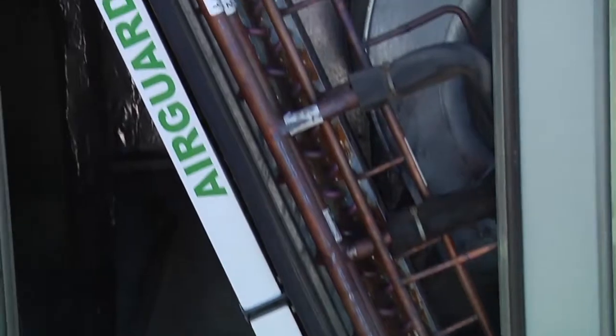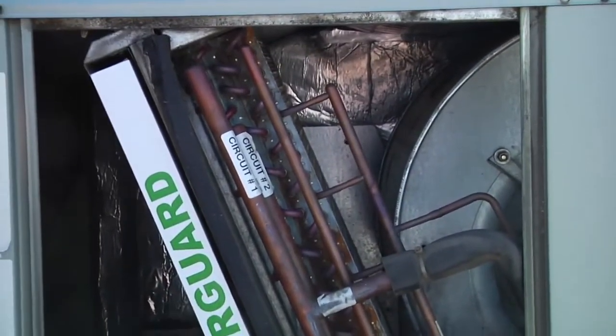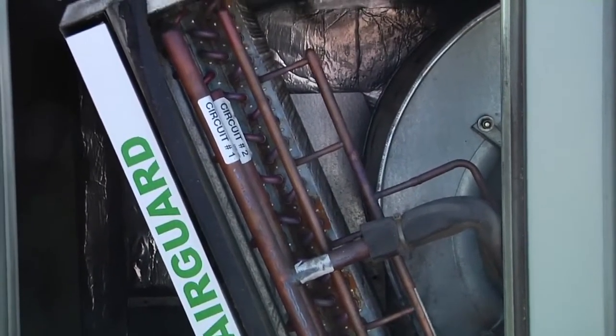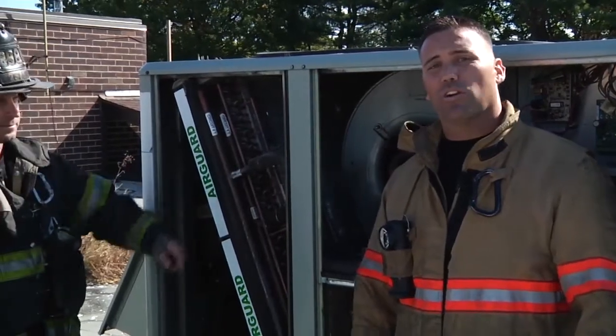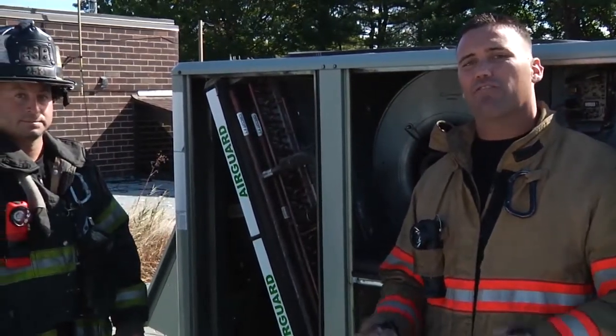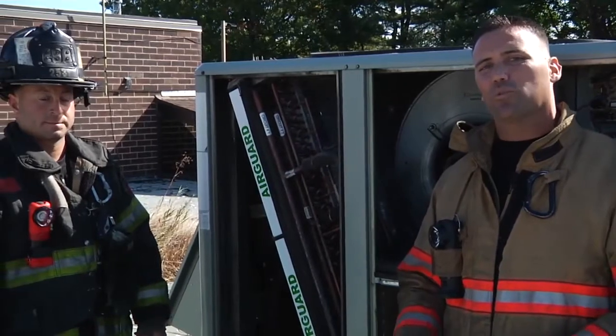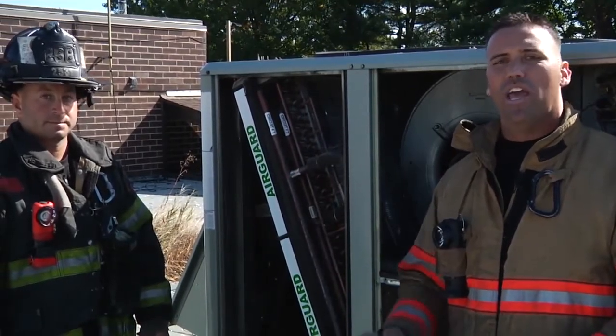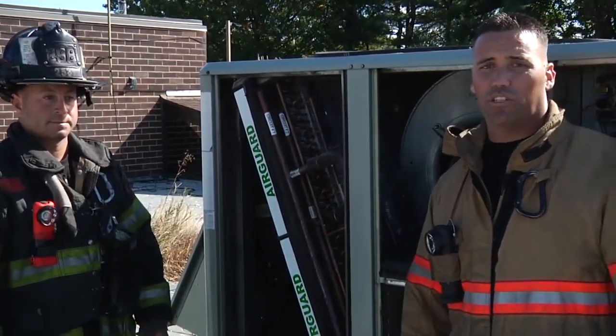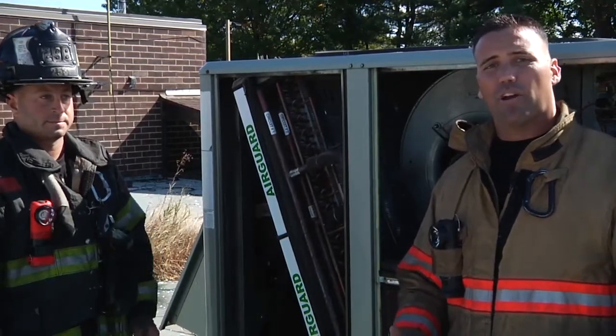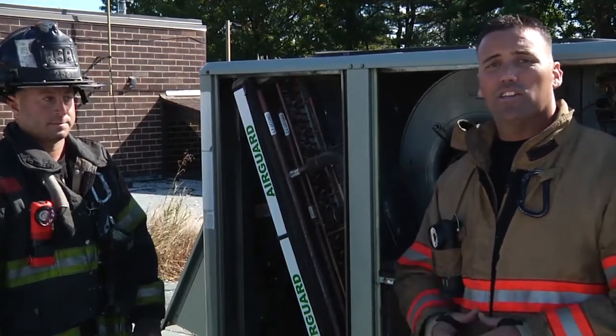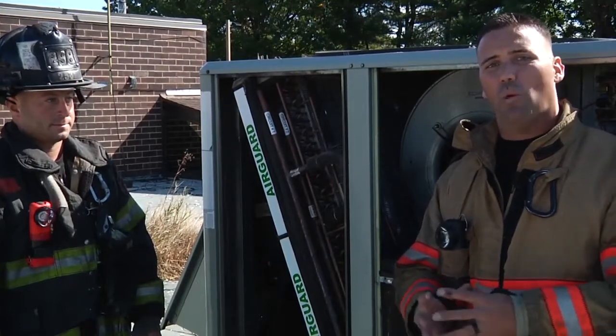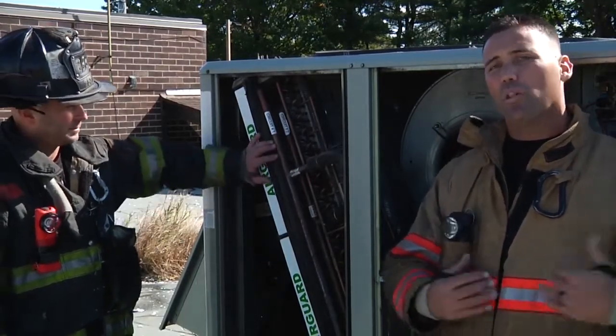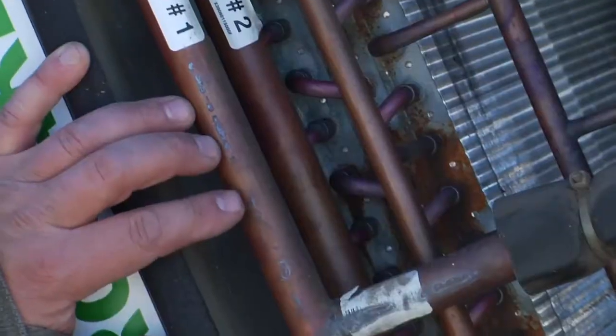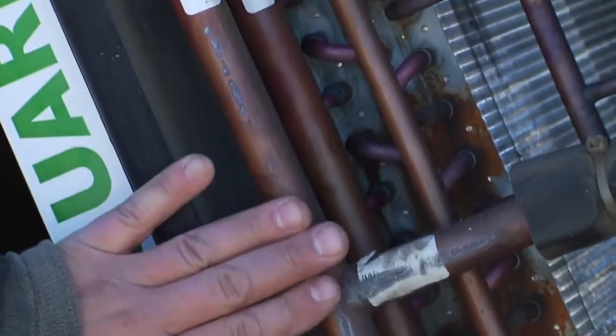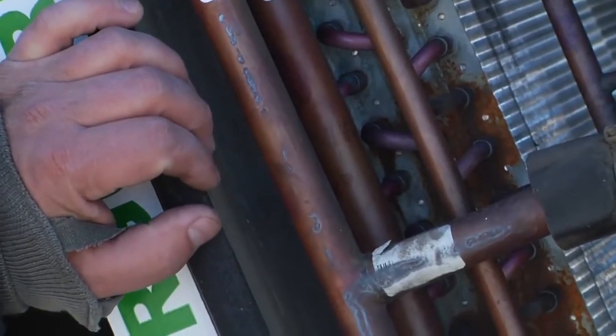It's a fallacy that HVAC systems actually cool the air. As the air passes over the evaporator coils, the coils actually extract the heat from the existing air, and that's what's actually cooling the air as it passes over and is pushed through the ductwork throughout the system. One way to identify the evaporator coils, besides seeing them, is locating the cold and the wet side. When the cooling function is on, these coils will be cold and they will be wet to the touch. And again, that's the evaporator and evaporator coils.